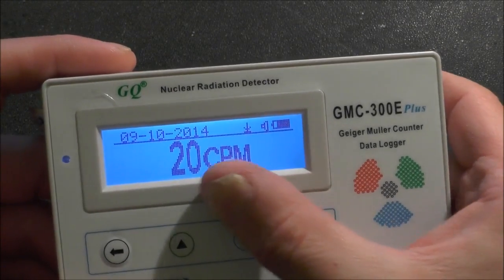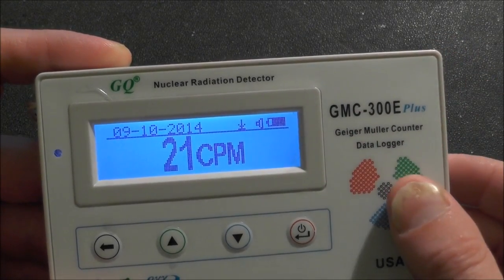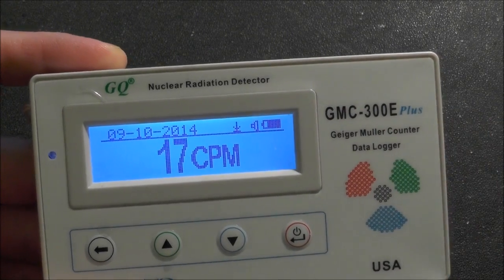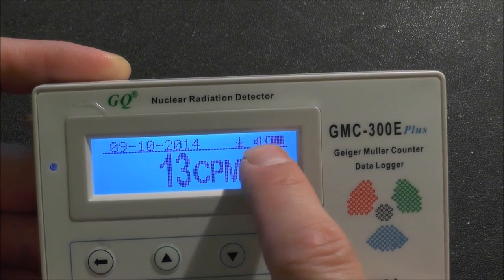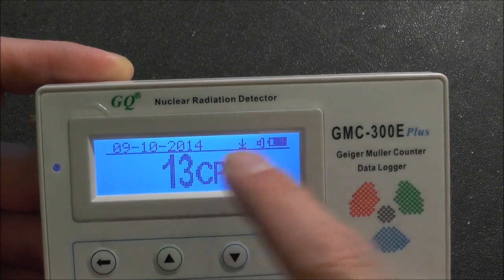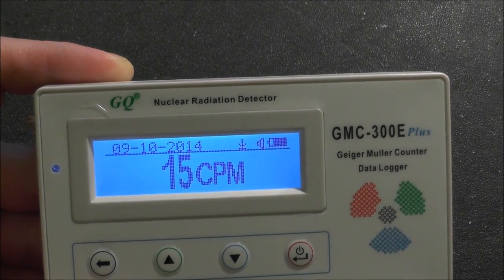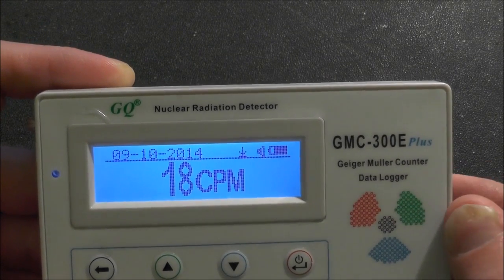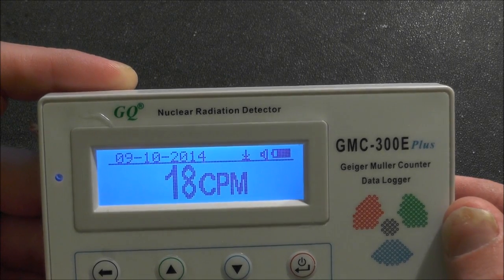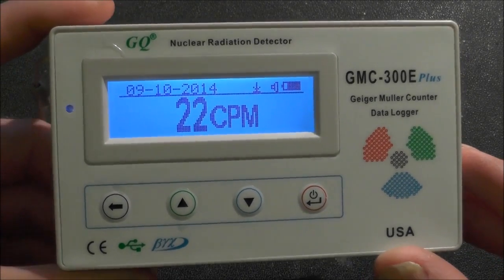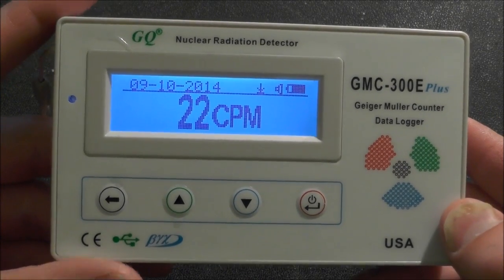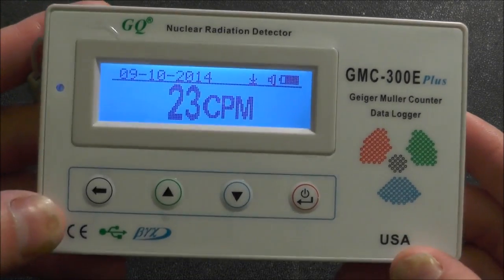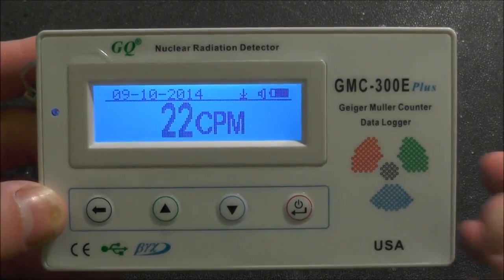So on the screen here you've got date along the way on the top there. You can change that easily to time. And you've got a few symbols here that sort of mirror the things you'd see on your mobile phone. So you've got a battery gauge, you've got a little speaker which means the clicker is on, that symbol there means that it's recording in the data log, and there's another symbol in there that looks like a little bell and that's the rate alarm which I've turned off at the moment.